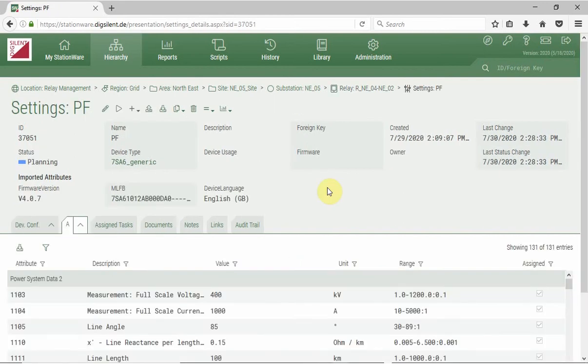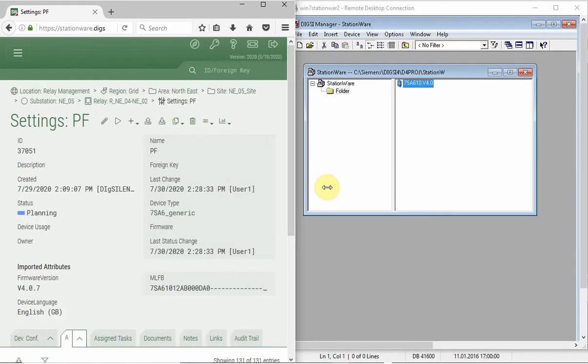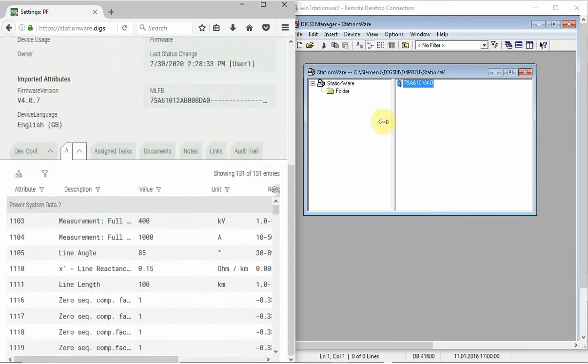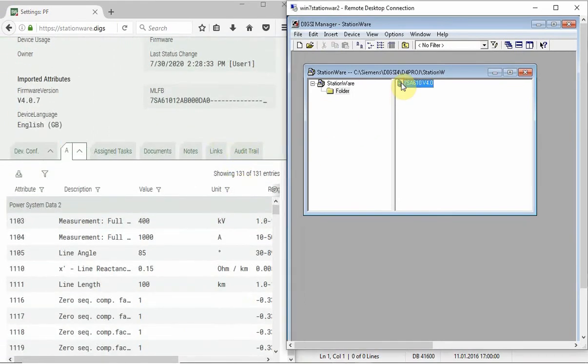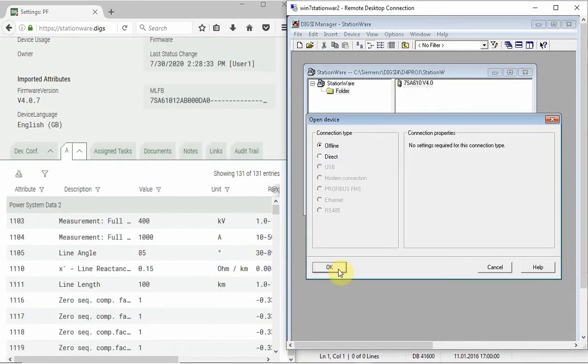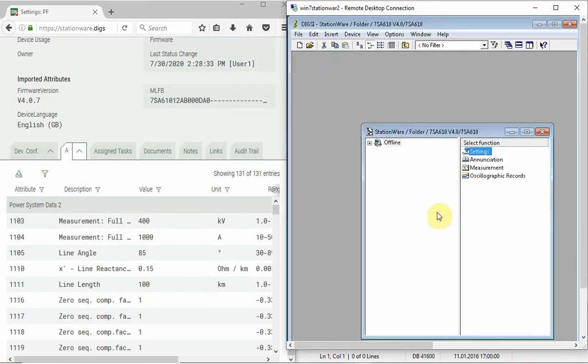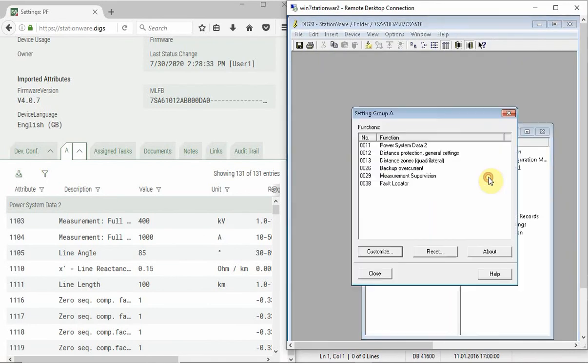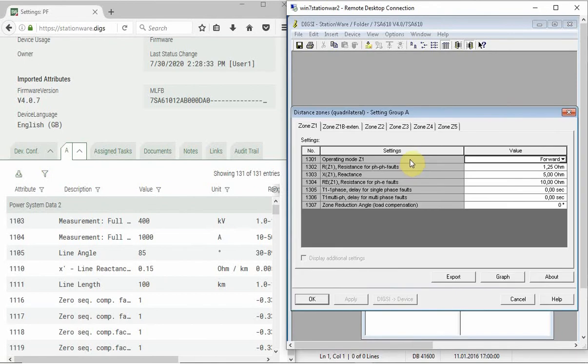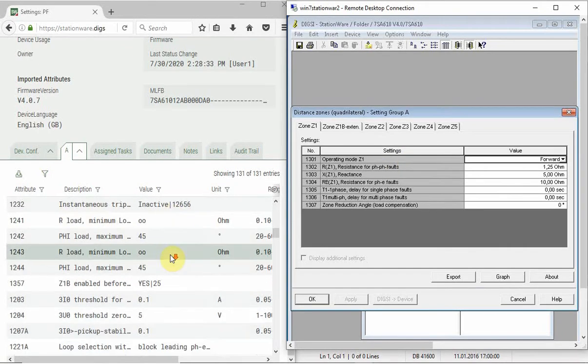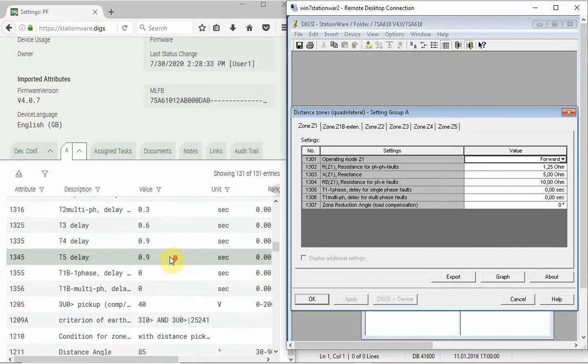Let us compare the settings in Stationware with those in the protection device-specific software. As you can see, the phase distance settings for all three active zones are different.